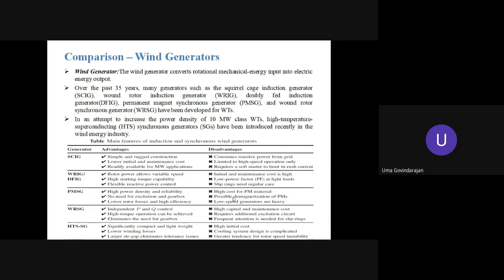Reactive power is a very, very important power. We all know that an induction machine can be modeled as a transformer. To establish the magnetic flux, the air gap flux, we require reactive power. In the case of the squirrel cage induction generator, the field flux, the air gap flux, is established using the reactive power drawn from the grid.